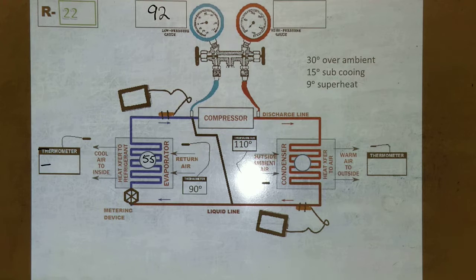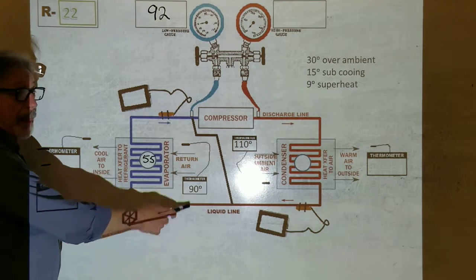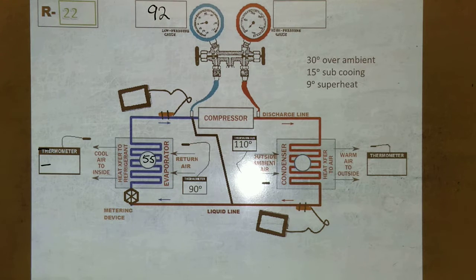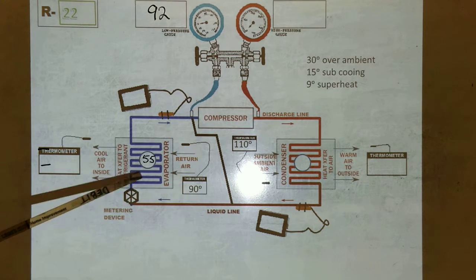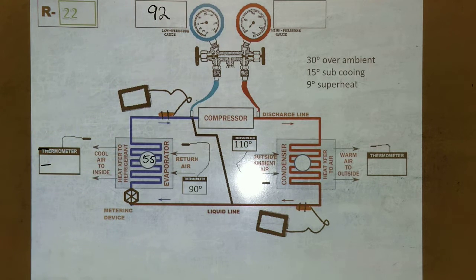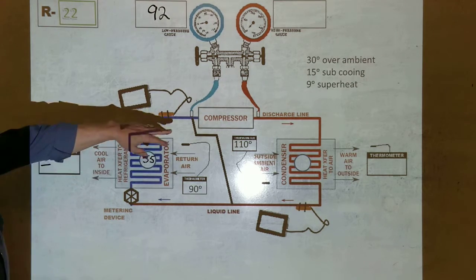Okay, so have we got that? Everybody follow the process we just did? Yes, sir. 90-degree ambient temperature in the house. That's probably what the thermostat is saying. So we can determine on the refrigerant what we should be reading on our pressure gauges, right? 20-degree difference from the other side. Right? Okay.